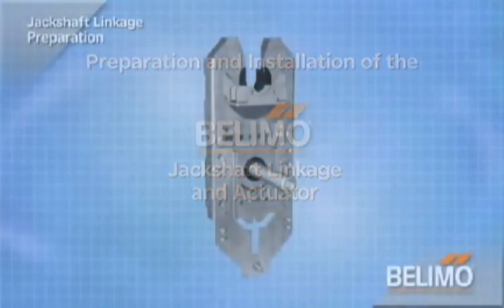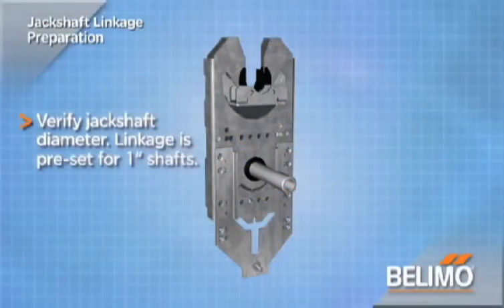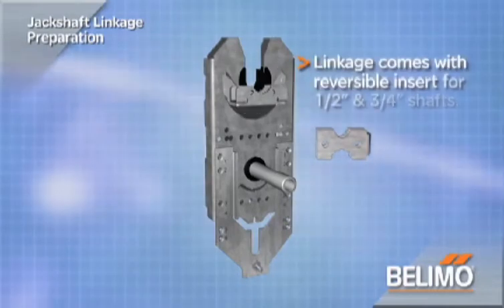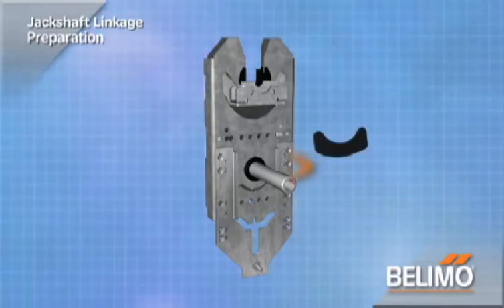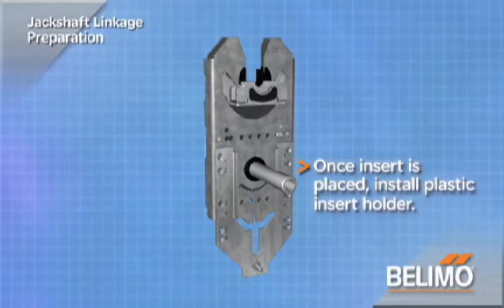Verify jack shaft diameter. The linkage is preset for 1 inch shafts, and the maximum diameter this linkage can accommodate is 1.05 inches. The linkage also includes a reversible metal insert for centering on 1/2 inch and 3/4 inch shafts. Once the insert is turned to the desired shaft size, install the plastic insert holder.